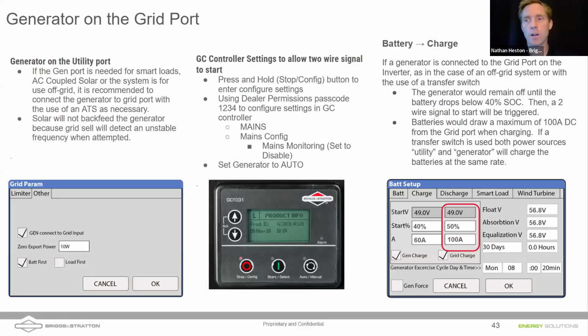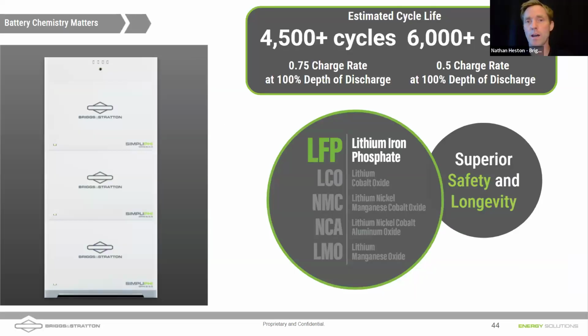So the generator has to cover the loads of the home and have enough available power. So if you have a smaller generator, keep this in mind, to also charge the battery at the rate you're specifying. So 100 amps at about, let's say we're charging at 56 volts, 100 amps at 56 volts is 5.6 kilowatts of power going to the batteries. If you've got a smaller generator, make sure you've got enough power left over to cover the home loads. Otherwise, you might have the generator shutting down.